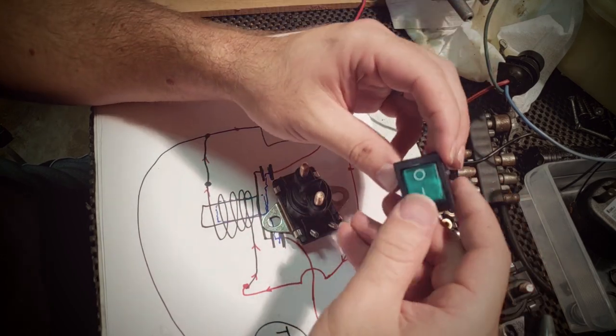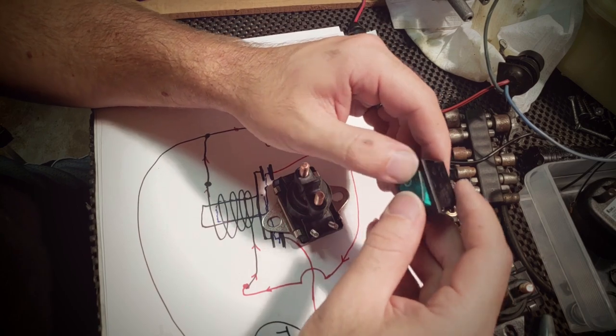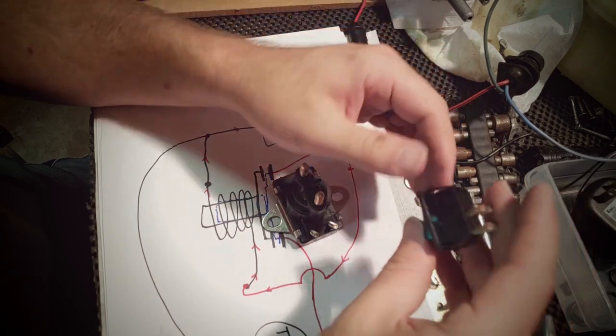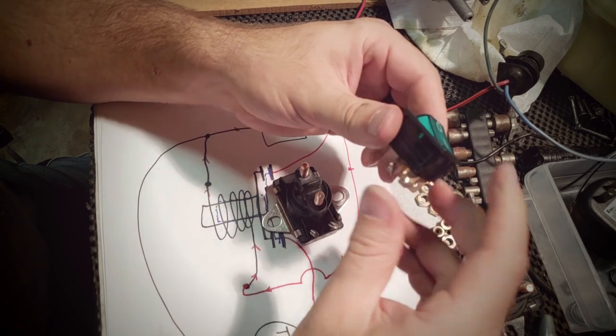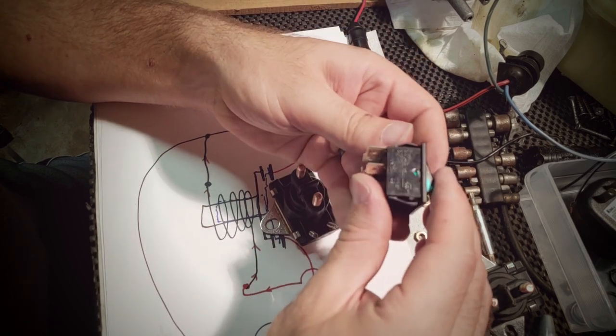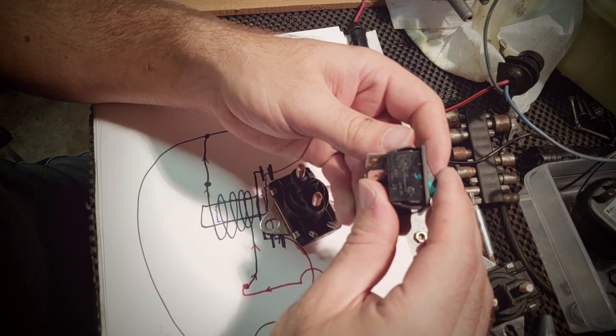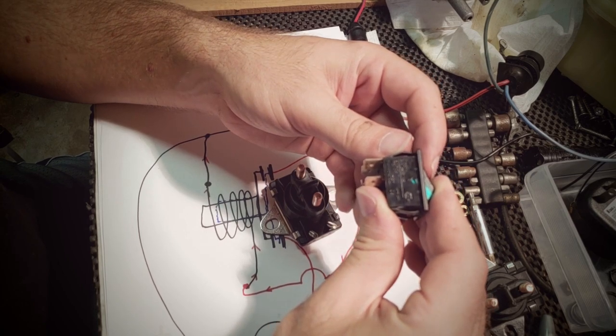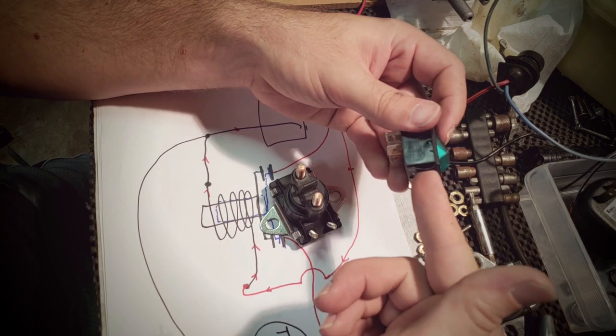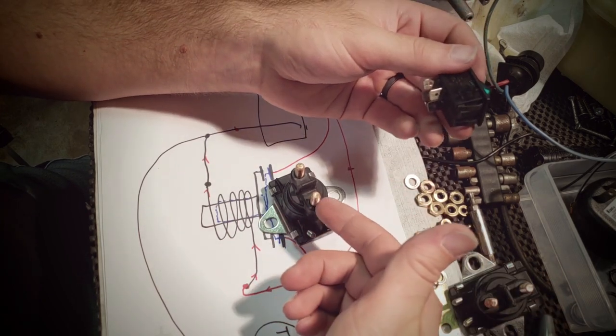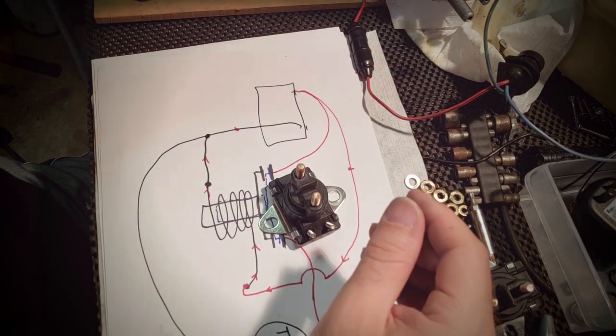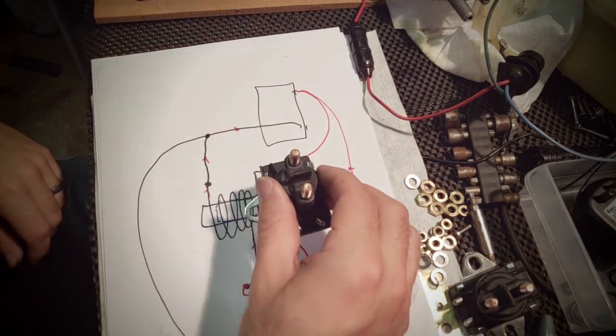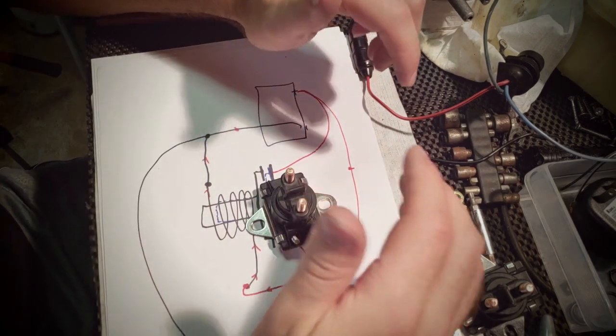And just for example, I mean, this would appear to be a really large switch that seems like maybe that could handle it. And it might. But I mean, just for reference, the rating on the switch is only 16 amps. So I mean, you got to put that in perspective 16 amps for this, this is taking over 100 amps. So I mean, it starts to all kind of add up as to why they actually do this.